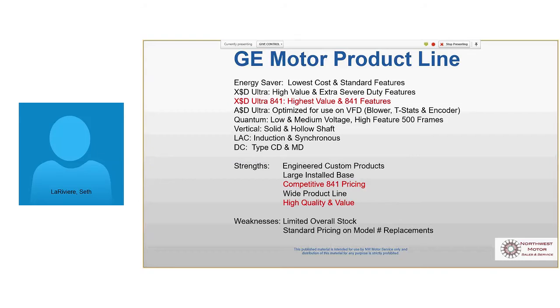If you look at the payback cost of a higher efficiency motor versus a standard efficiency motor, it's usually a poor decision to go with the cheapest, lowest cost, because motors don't cost that much. I mean, you might spend a couple of grand on a 100 horsepower motor. Well, that motor consumes about $75,000 of energy in its first year of operation.